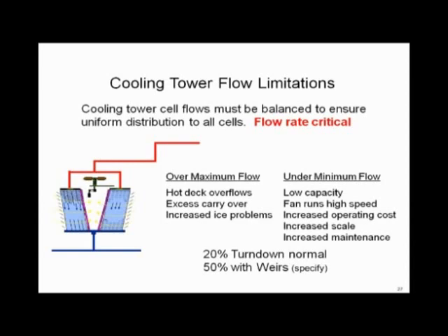What kind of issues? You lose cooling capacity — you can't get the tonnage, you can't evaporate the required pound of water per 15,000 BTUs per ton, and your fans run on high speed. If you don't put enough water to the fill of a cooling tower, the fans speed up trying to maintain leaving condenser water temperatures, and operating costs go up. More scale, more rocks, more maintenance — all bad things.